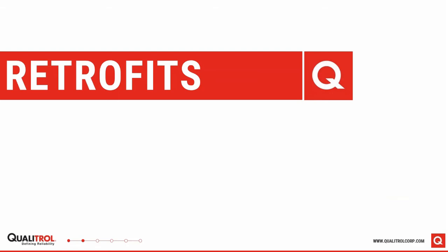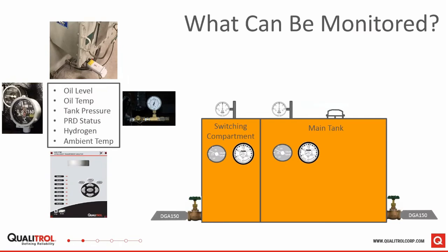And so now I'm going to talk about the physical side. It's great to say we've got all this good information coming back from the vault, but how do we get that information? You can easily order monitoring equipment on new transformers, but any amount of new transformers that you install are an extremely small percentage of the total that you have installed. And so the majority of the work to install monitoring on vault transformers is going to involve retrofits. We've got some pictures here of some actual installations.